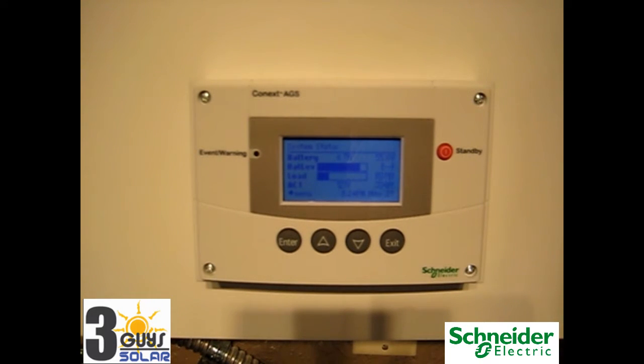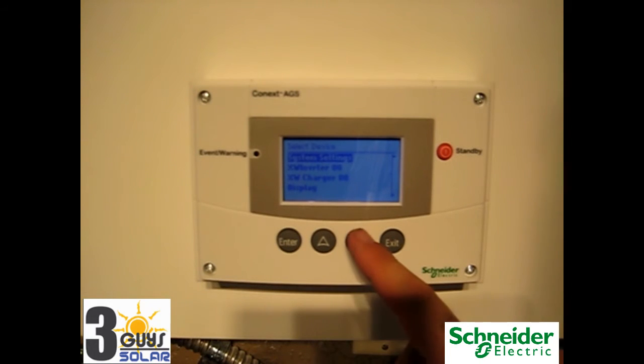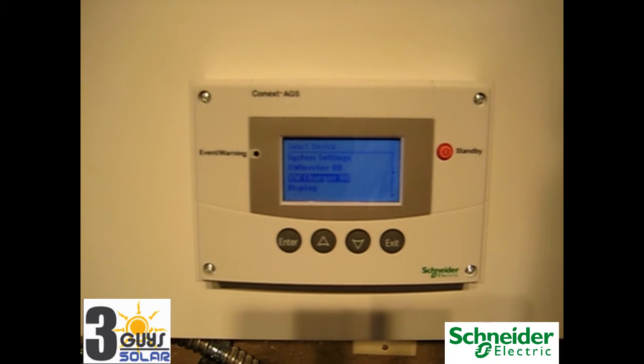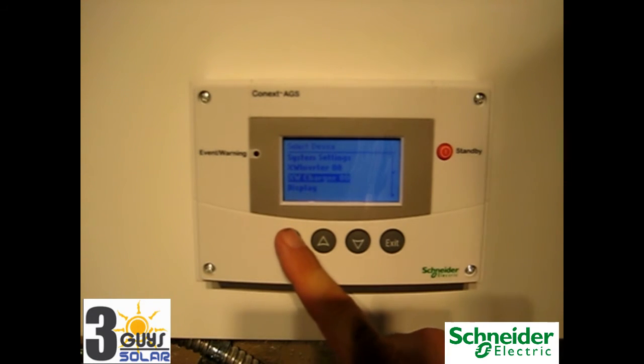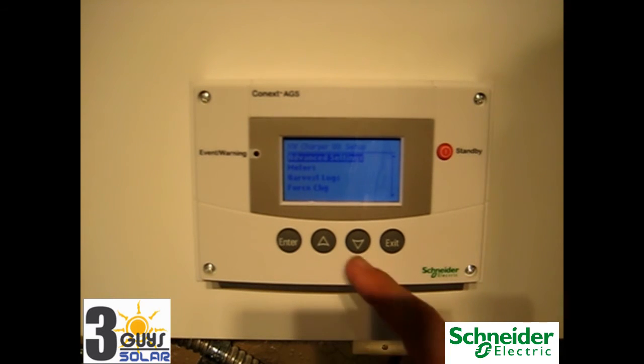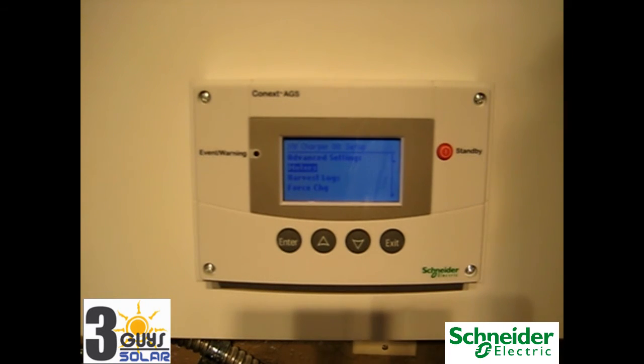A common question that I receive quite a bit is, how much is the solar producing and what is the solar doing currently? So from the system status screen, you're going to press enter. That'll take us to the select device screen. We're going to scroll down to the charge controller. Remember, the charge controller is our converter from PV energy into battery energy. We're going to press XW charger. Then we can come down to meters. That's going to give us the real-time information of what the system is producing.